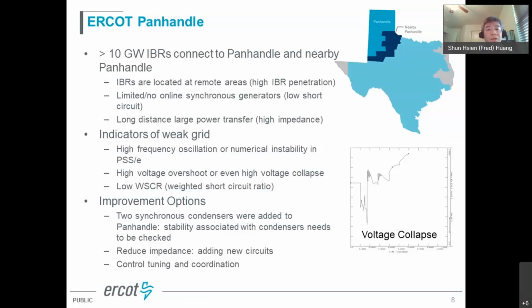That's also another hint that the system is getting weaker. Or you can simply run a short circuit analysis to look at the short circuit current versus the capacity in the area. That may also provide information on potential weak grid conditions.